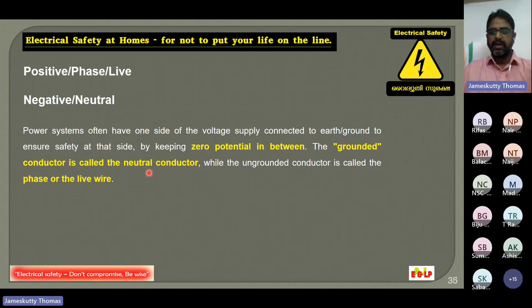Now, as I told you, it is a distribution transformer. I told you for a single phase connection, phase and neutral wires will be there. This neutral point, actually we are not getting it from either the generating station or the substation. We are not getting neutral from anywhere. We are creating this neutral point here in this distribution transformer itself. Let us see how and what for it is created.